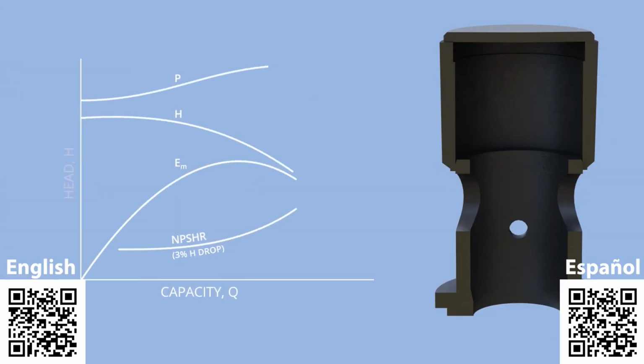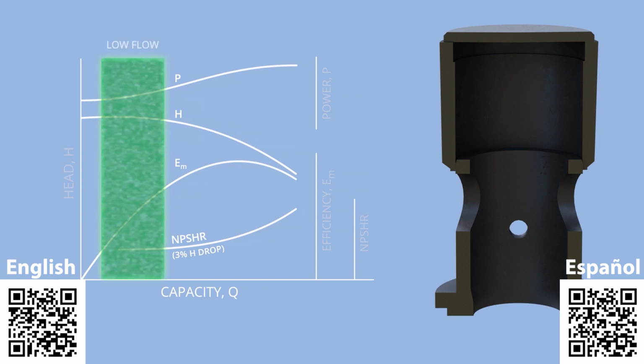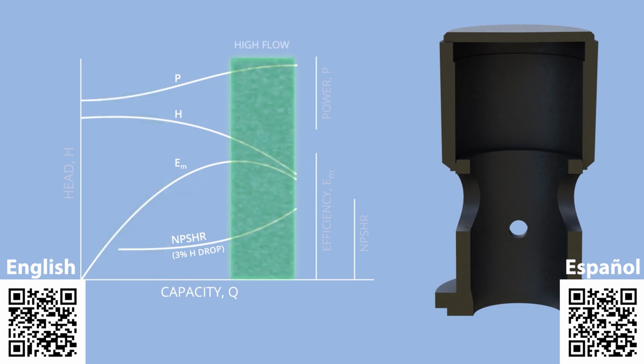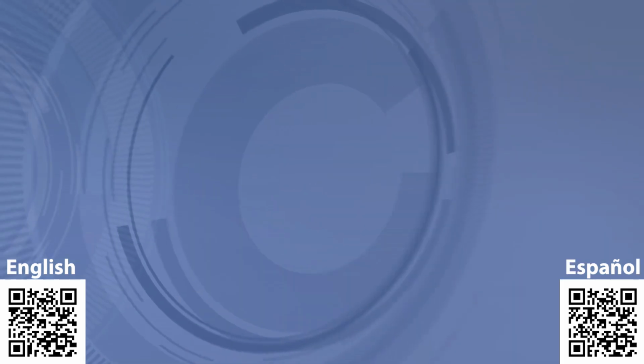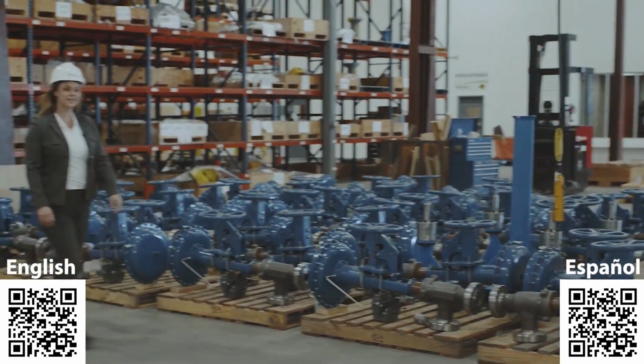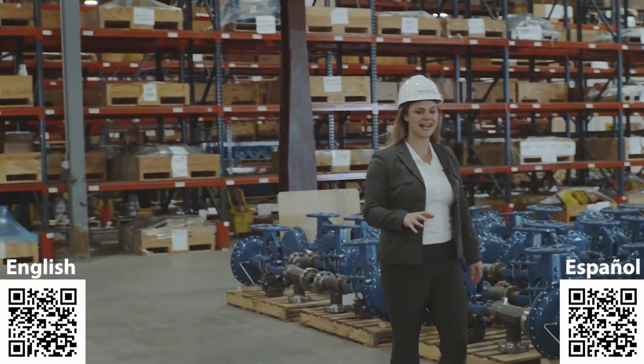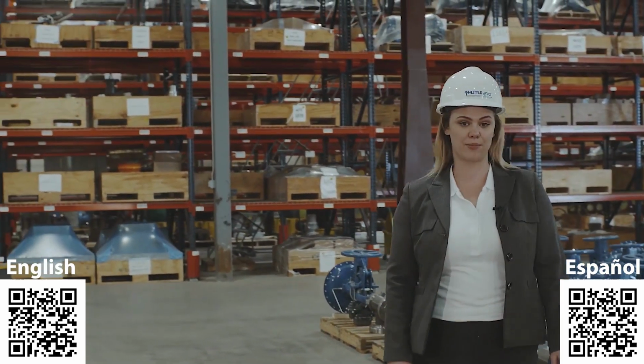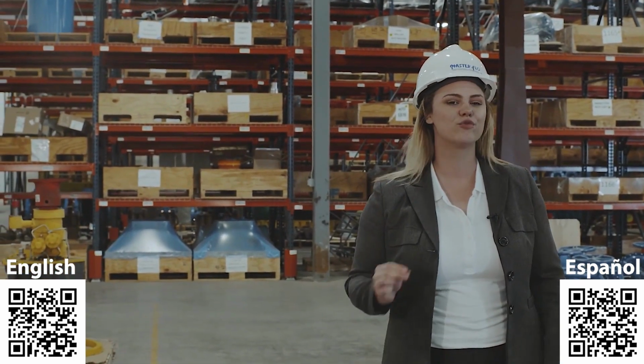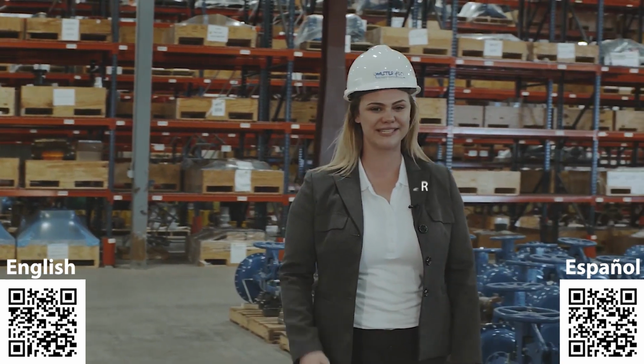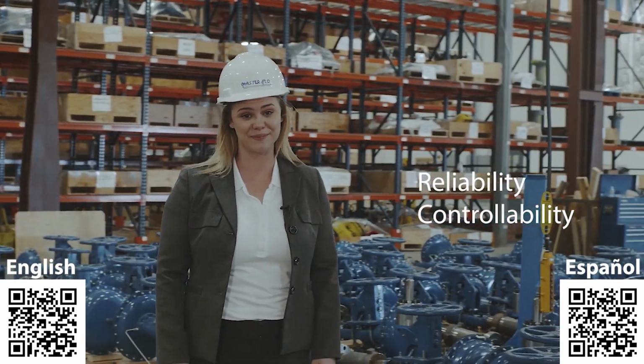MasterFlow's custom trims can be designed for a specific pump curve, providing high loss coefficients at low flows and low loss coefficients at high flows. Custom trims allow you to eliminate the need for parallel valve operation and therefore reduce maintenance while increasing reliability and controllability.